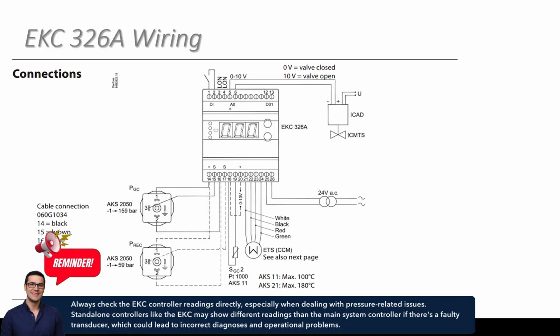Yeah, definitely. And we do have the display, which is a big help, but you want to compare that and then work down from there. And if it does get to the point that you have to take a meter and go right to seeing if you've got voltage there or not, and if it's within that proper range, then those are definitely some troubleshooting steps that you want to keep in mind.